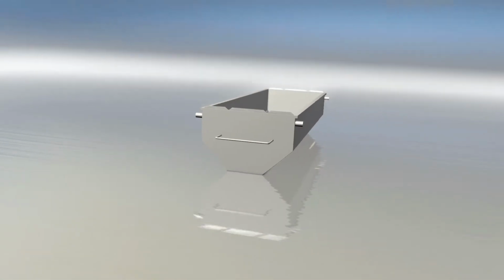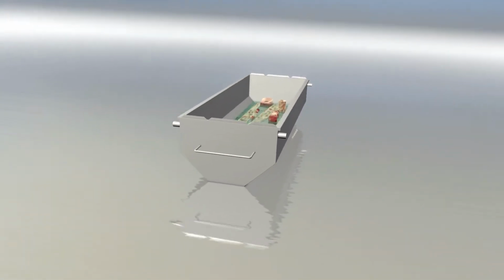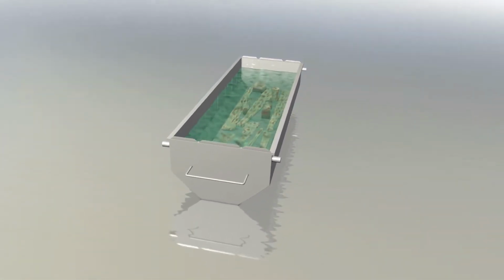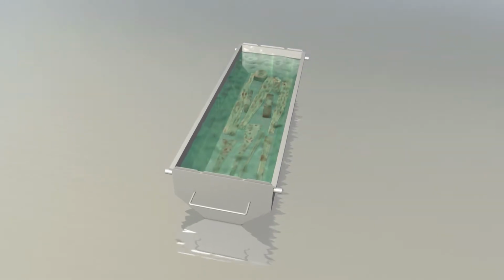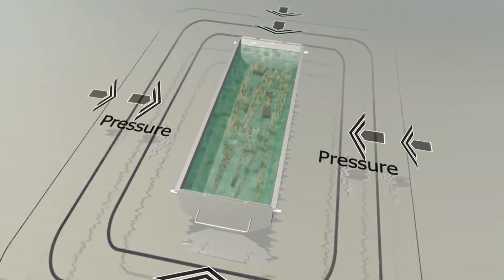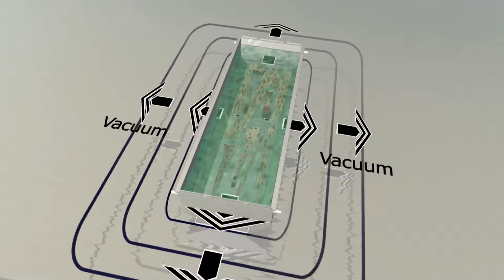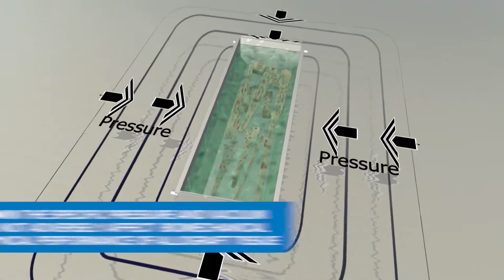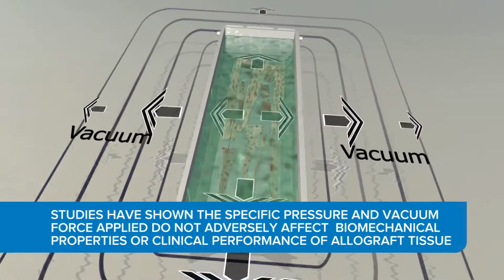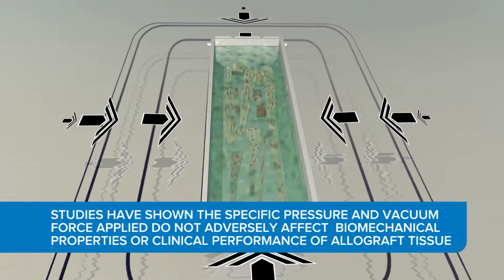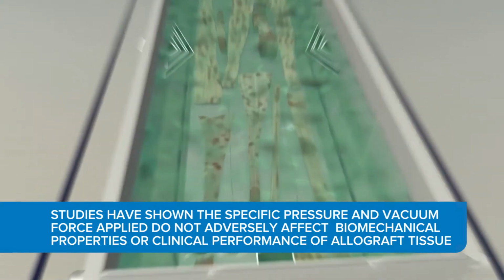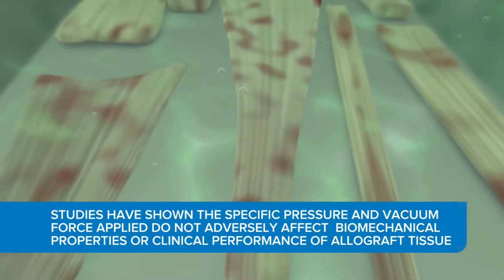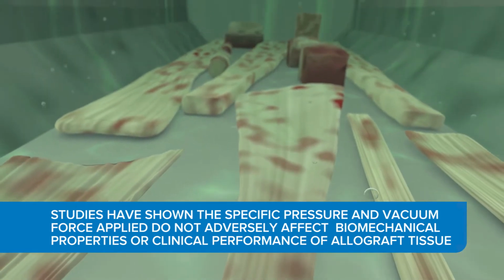In the initial phase of the process, mild detergents and sterilants fill the BioCleanse processing chamber. A series of mechanical oscillations consisting of alternating pressure and vacuum cycles are then applied. Studies have shown the specific pressure and vacuum force applied during the BioCleanse process do not adversely affect the biomechanical properties or clinical performance of allograft tissue.